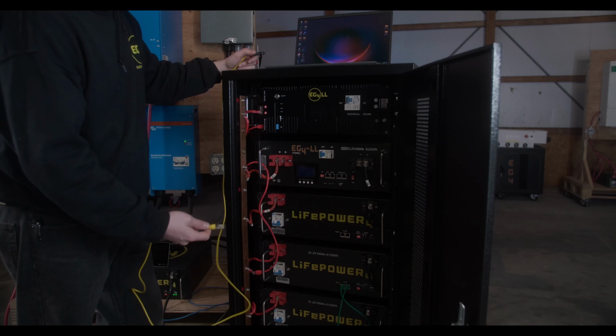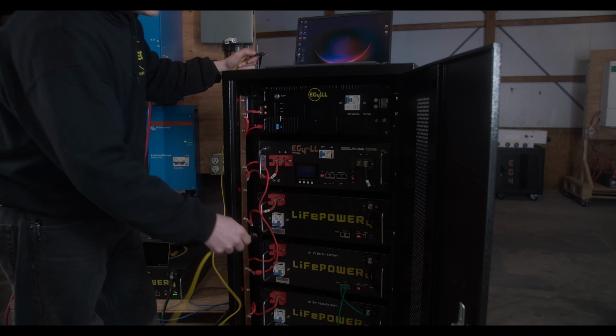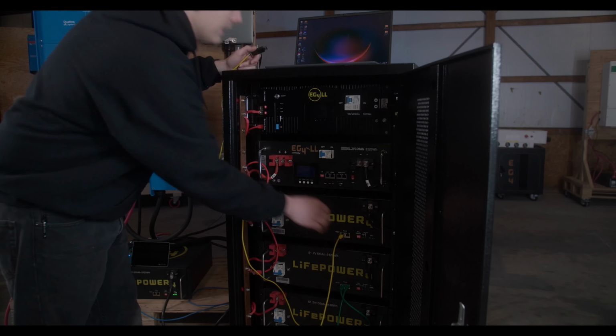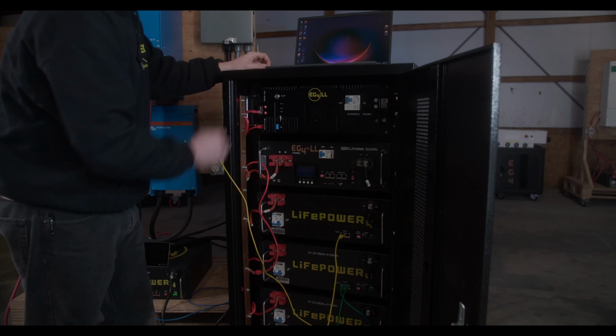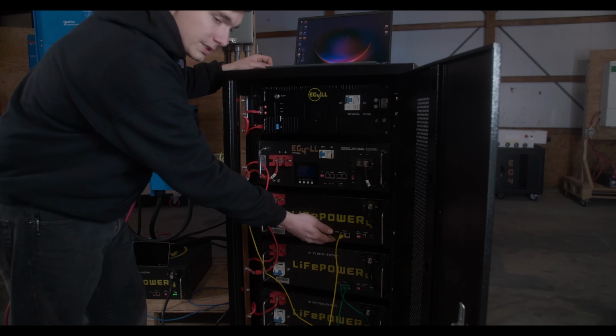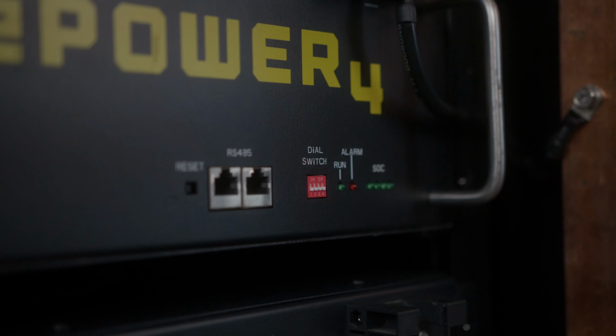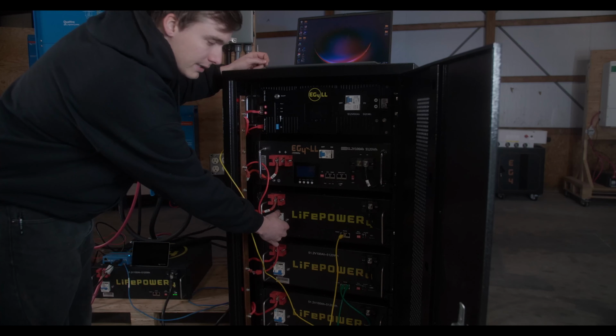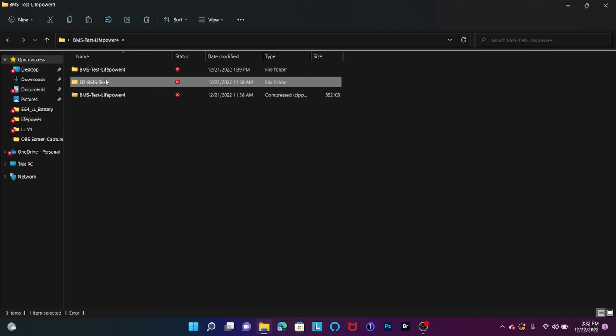For our LiFePOWER4, we're going to go ahead and take our cable and plug it into the RS485 and the USB of our laptop. We're going to make sure also all of our dip switches are set down to the 0 position, and then we're going to turn on our breaker and our BMS. For our LiFePOWER4 update, we're going to go to BMS Test. Here's our BMS Test application.